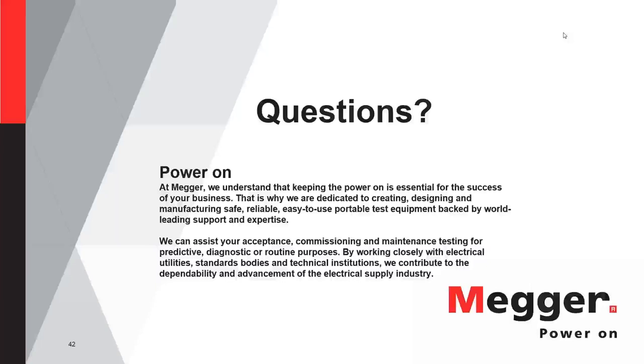It becomes more of a problem when you actually want to do fault locating, because you have quite a bit of, let's say, capacitance in these circuits. The wind farm circuits are known for that because they are 1,000 MCM, 1,500 MCM cables, and they're long. It's not very scientific, but the experience has proven this over basically half a century.